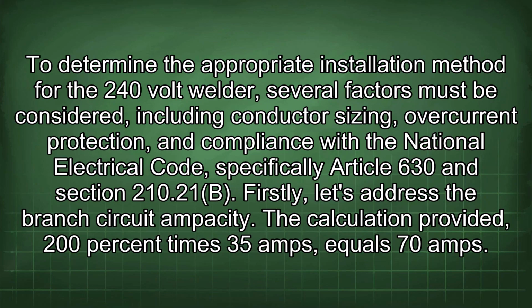To determine the appropriate installation method for the 240-volt welder, several factors must be considered, including conductor sizing, overcurrent protection, and compliance with the National Electrical Code, specifically Article 630 and Section 210.21(B). Firstly, let's address the branch circuit ampacity.